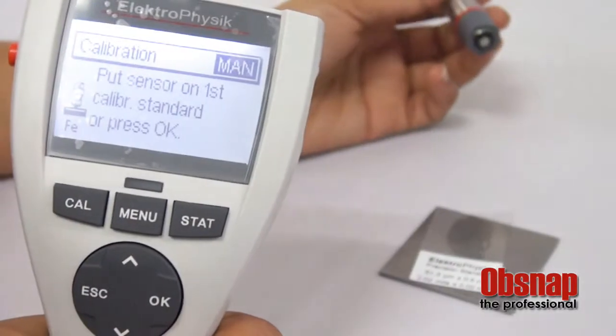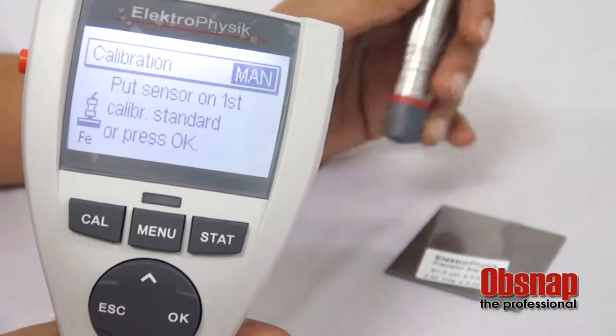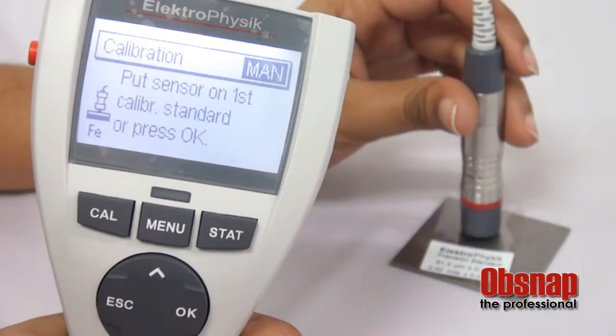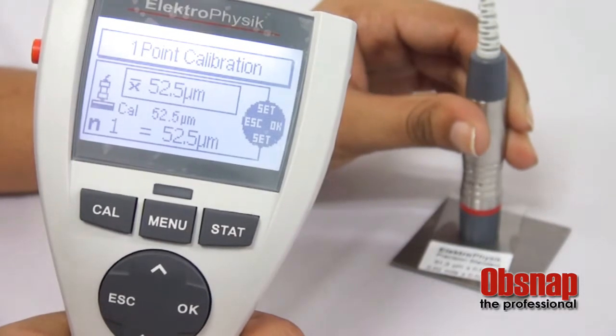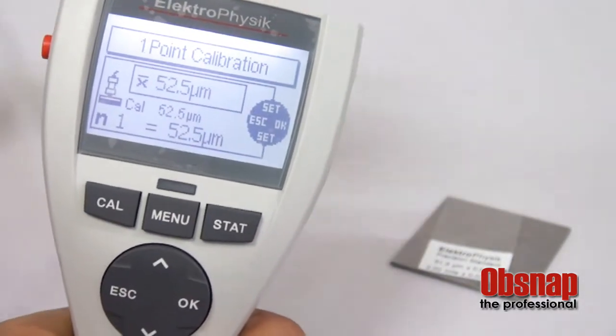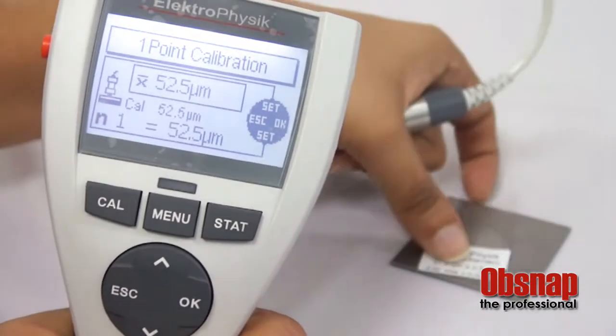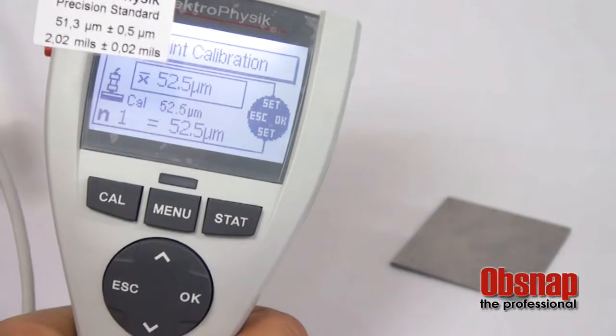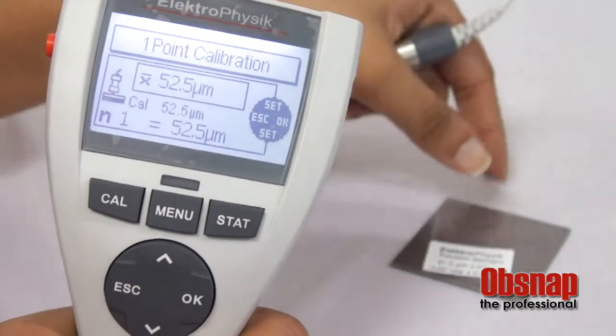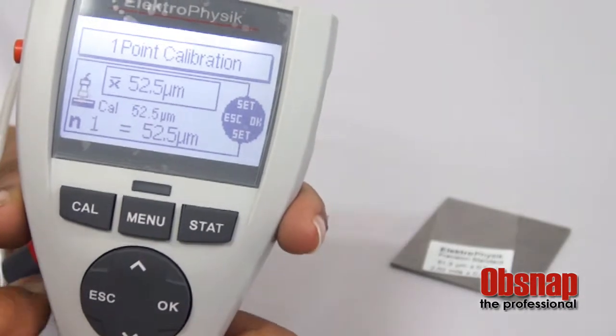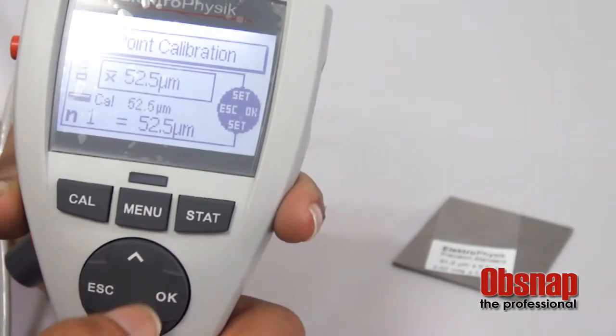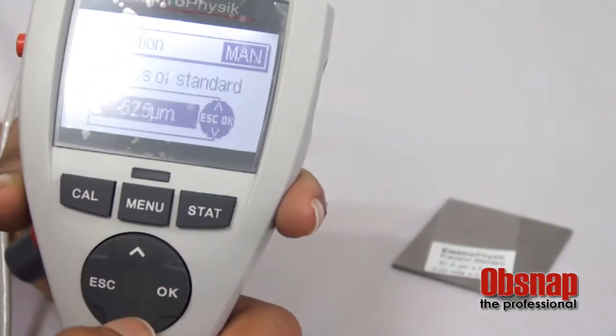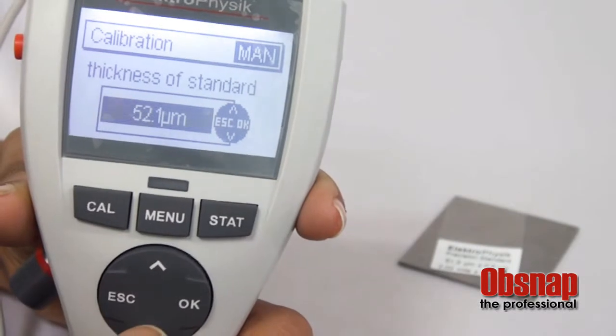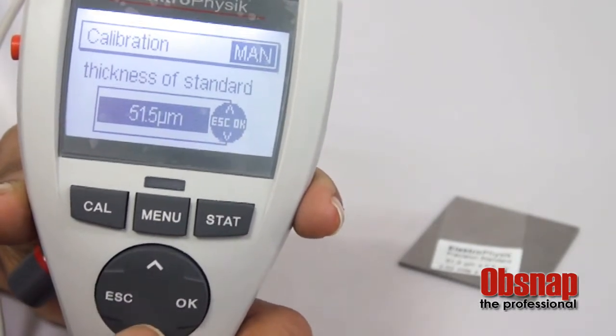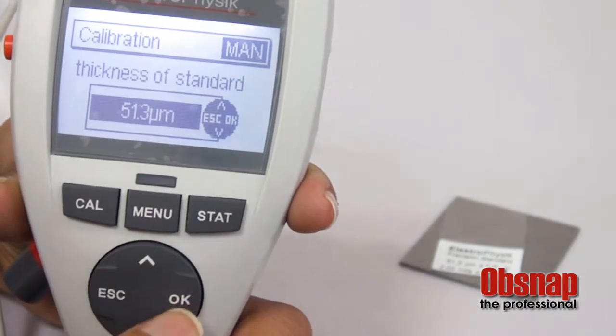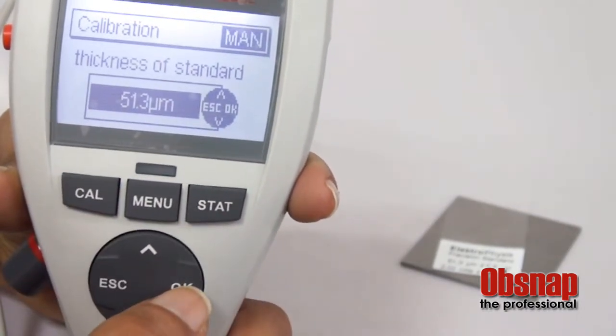Then put the sensor on the first standard calibration foil. When you put it, it will display the reading, which is 52.5 micrometer. According to the precision standard, it is supposed to be 51.3 micrometer. So we can adjust this reading by pressing on this upper and lower arrow. We set the reading according to the standard precision foil. Right now, after we do the setting, we can click OK.